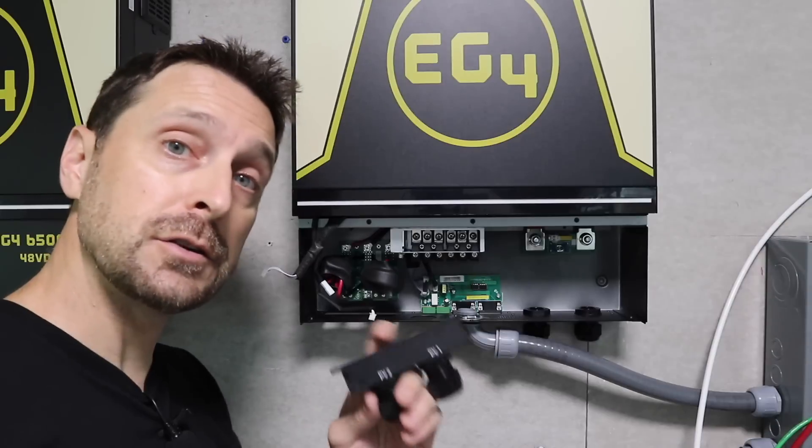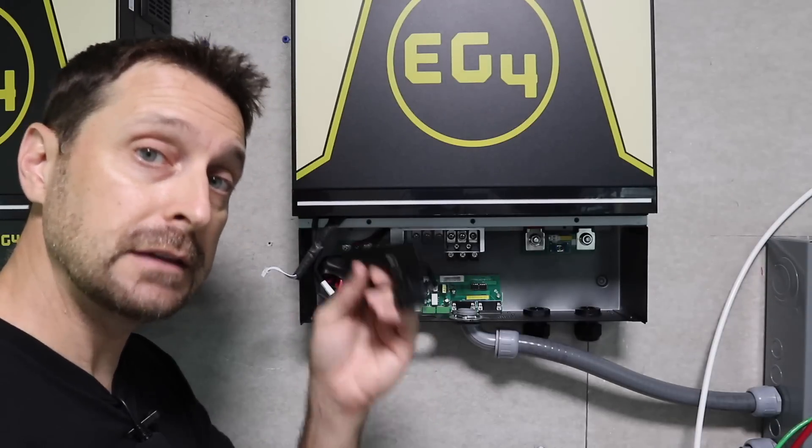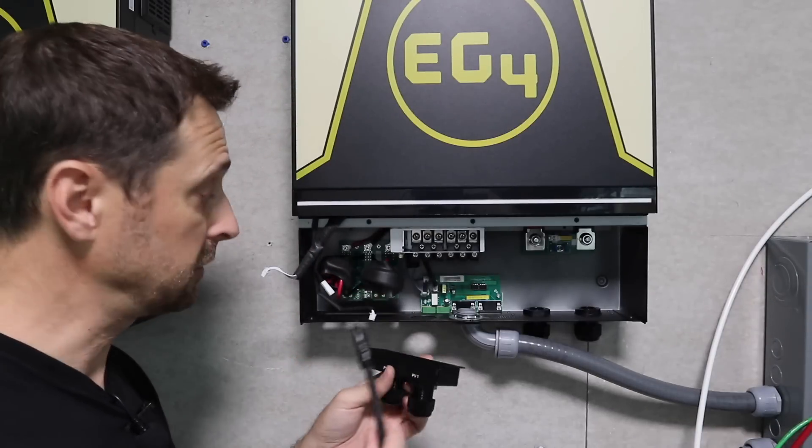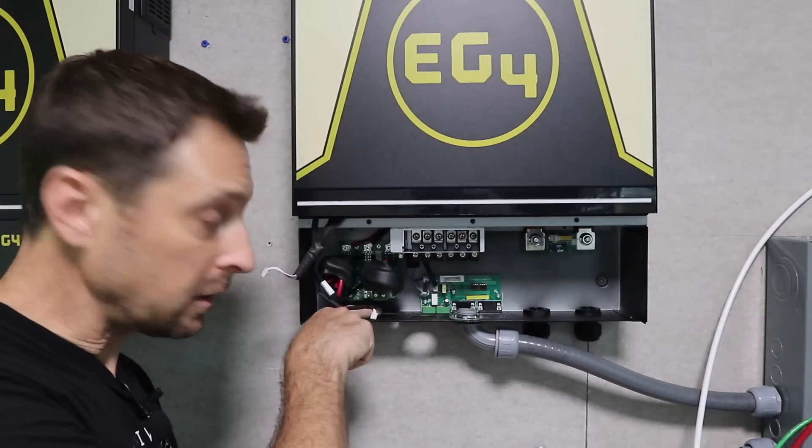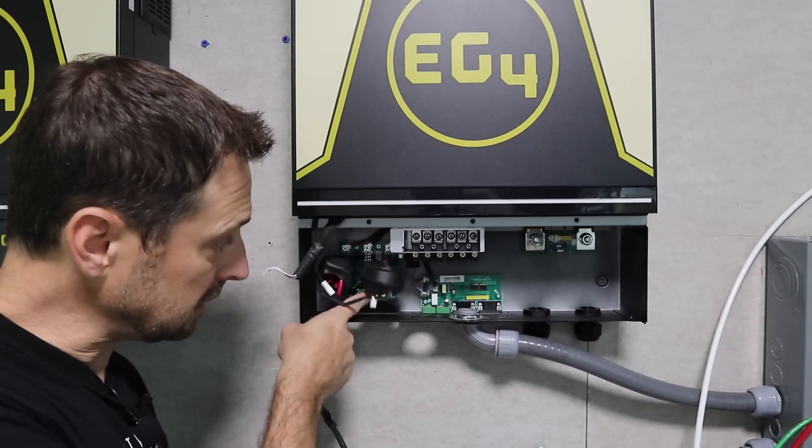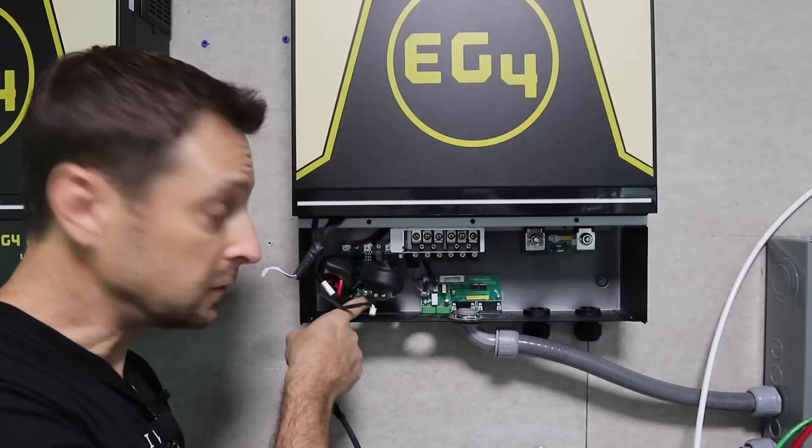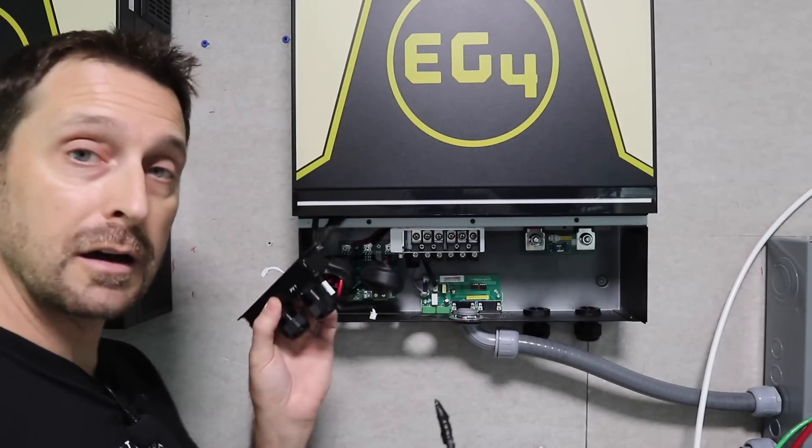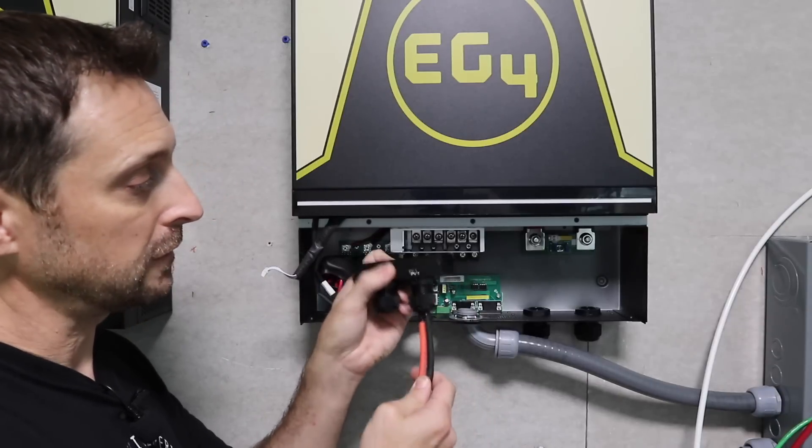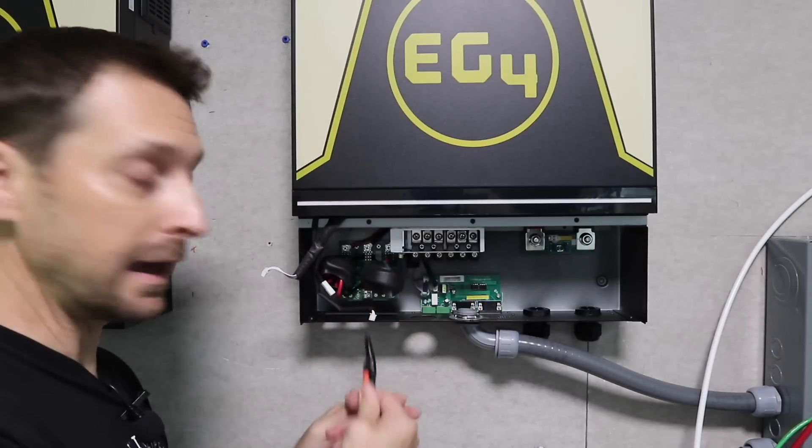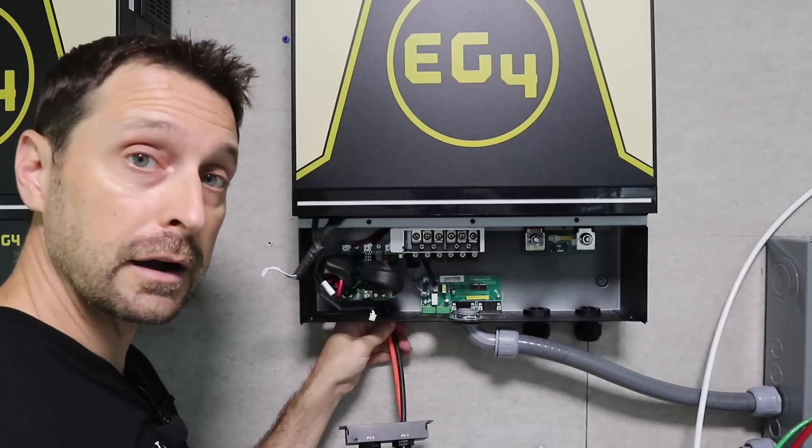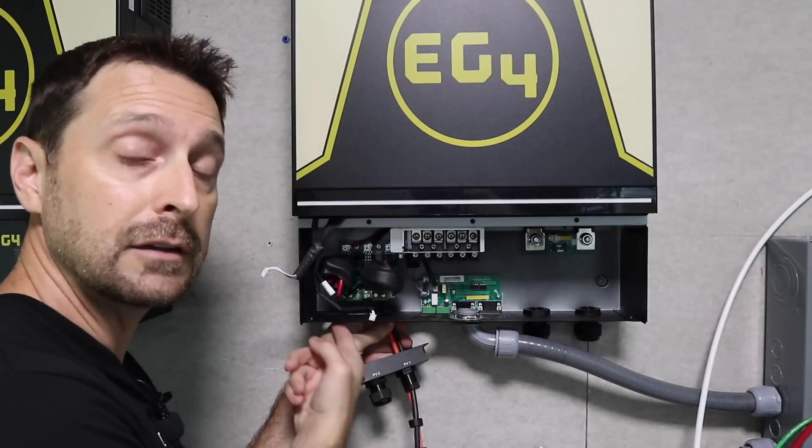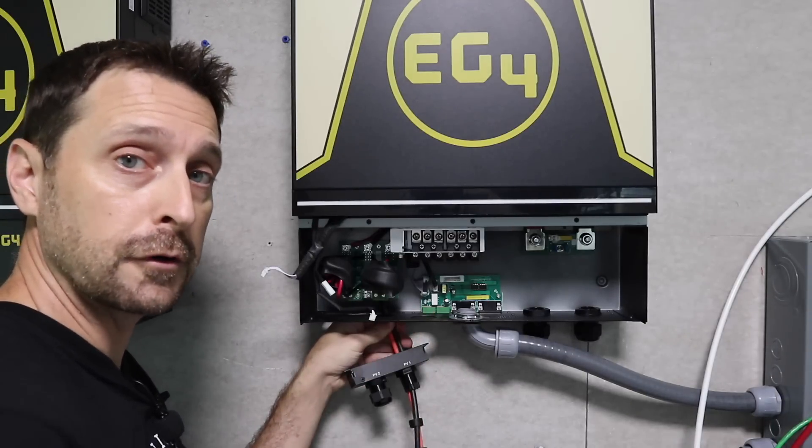Here's a little trick. This little plate for the PV connectors needs to come off for you to insert your PV wires. There is hardly any space to get your fingers in there to connect those PV wires to these terminals. Taking this off is way easier. So take it off, slide it in there, let it hang, connect your wires, and then slide this up into place and screw it into the bottom of the inverter.